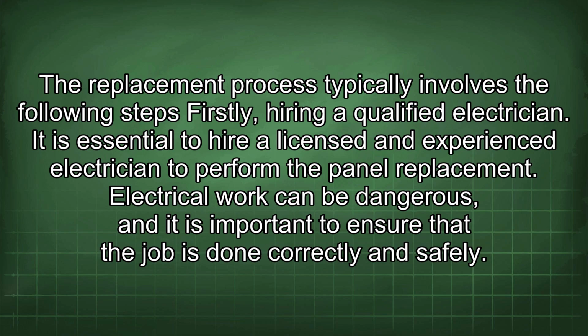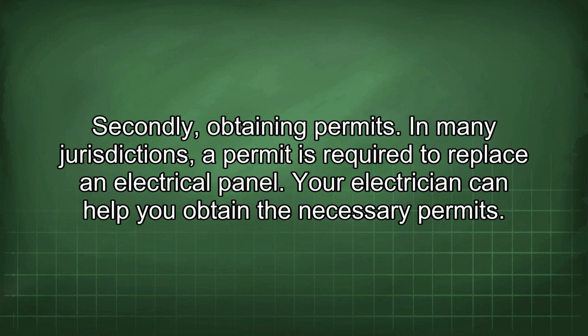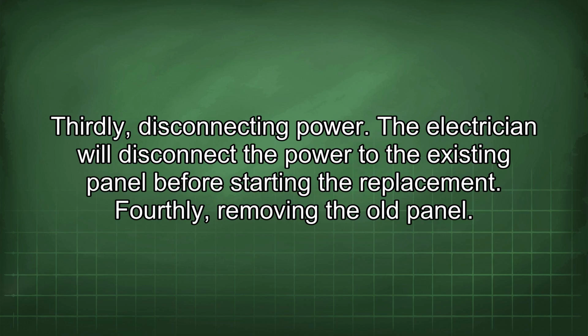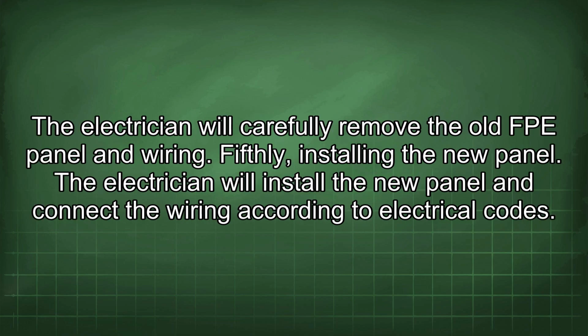The replacement process typically involves the following steps. Firstly, hiring a qualified electrician. It is essential to hire a licensed and experienced electrician to perform the panel replacement. Electrical work can be dangerous, and it is important to ensure that the job is done correctly and safely. Secondly, obtaining permits. In many jurisdictions, a permit is required to replace an electrical panel. Your electrician can help you obtain the necessary permits. Thirdly, disconnecting power. The electrician will disconnect the power to the existing panel before starting the replacement. Fourthly, removing the old panel. The electrician will carefully remove the old FPE panel and wiring.